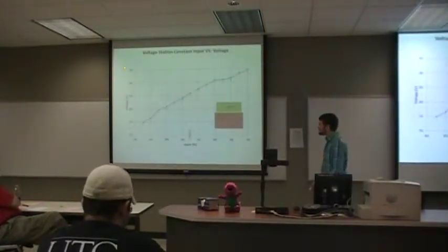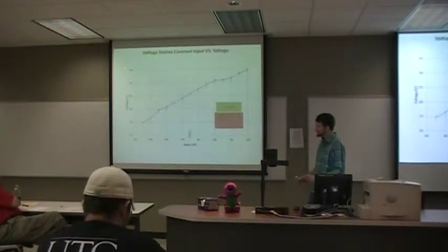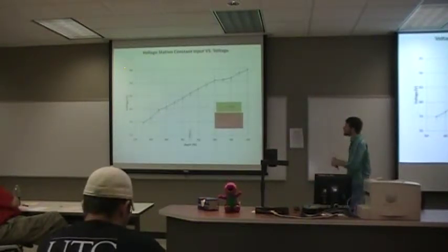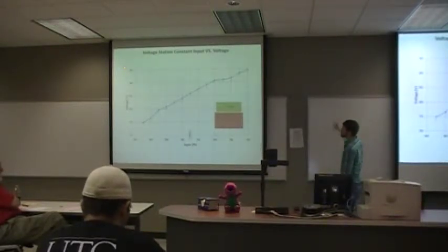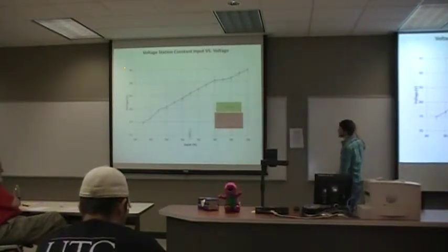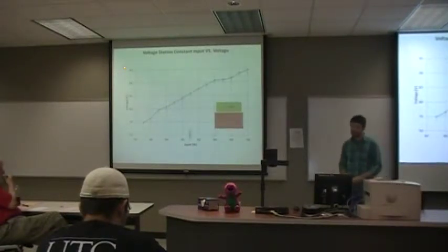So originally our very picky customer, this guy right here, said that this point right here was terrible because it was showing up like right here. So we tested this thing over and over again. What we kind of concluded was, if you first run the test, you go up, it starts ramping up to, what do we want, output of 80, goes up, gets there. Now if you keep running other experiments and you have it go past 80, you have it go to the highest output you got, which is 95, and then you tell it to go back and run another test to get this value, it's going to do something like this, and you're not going to get the same value. So that was very, very challenging here.